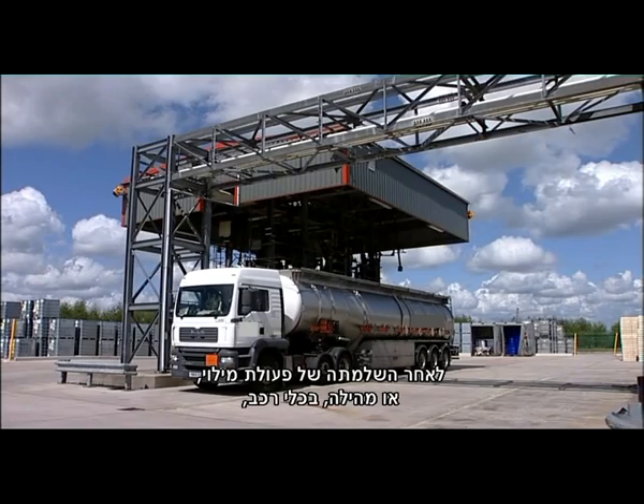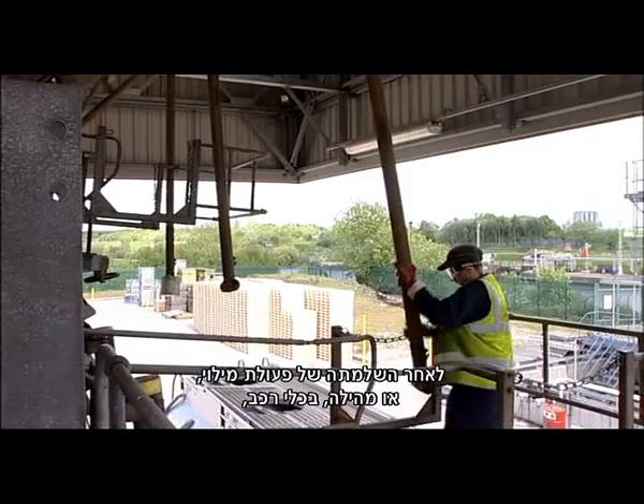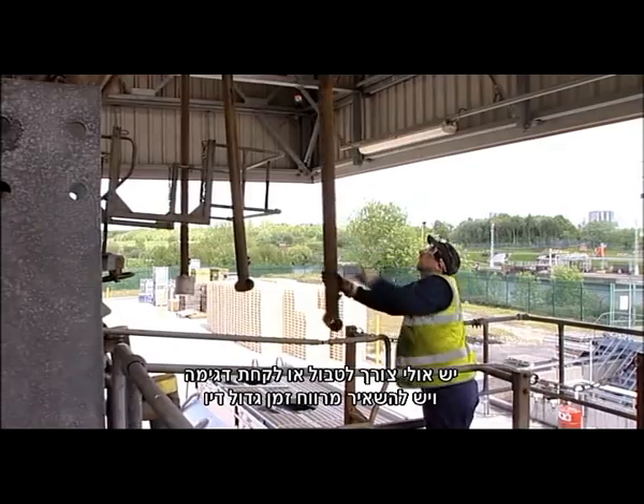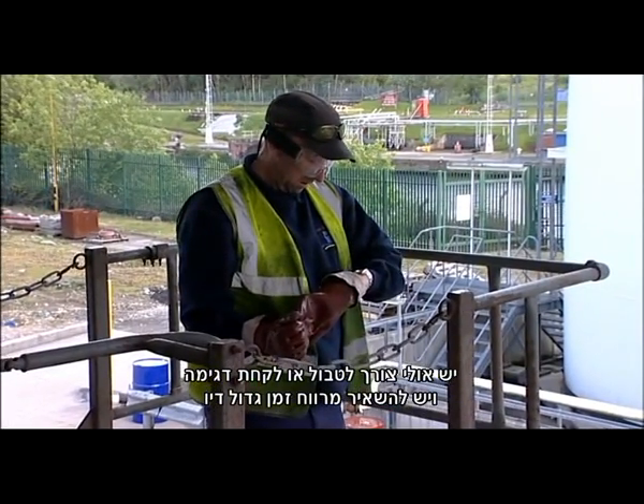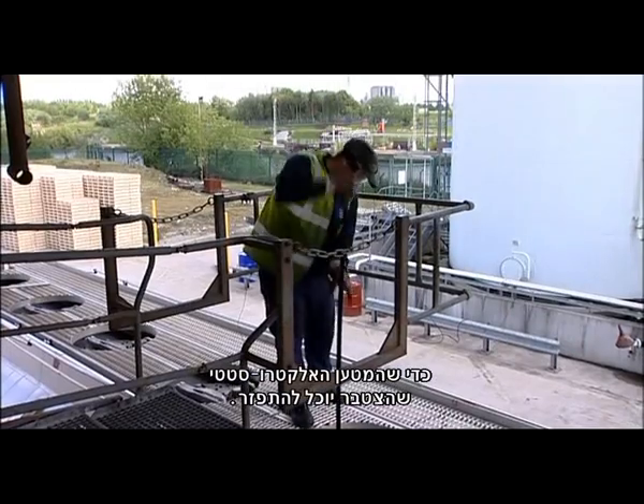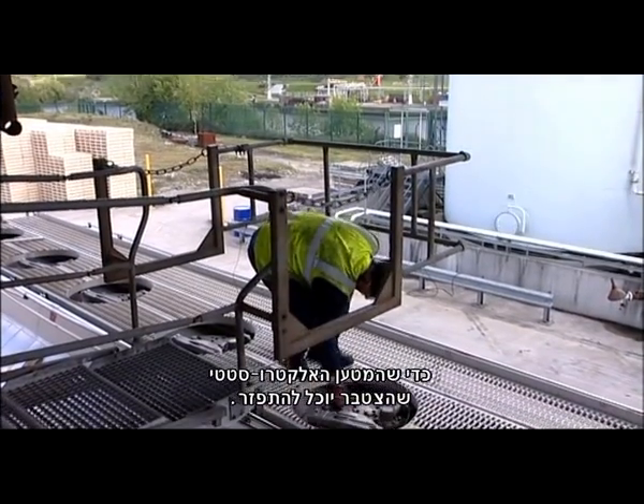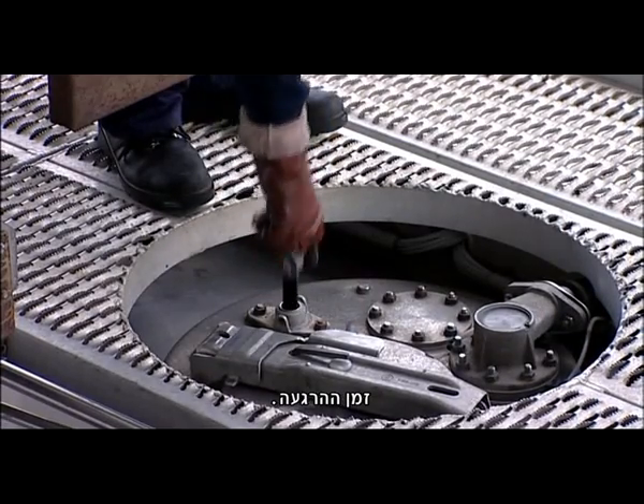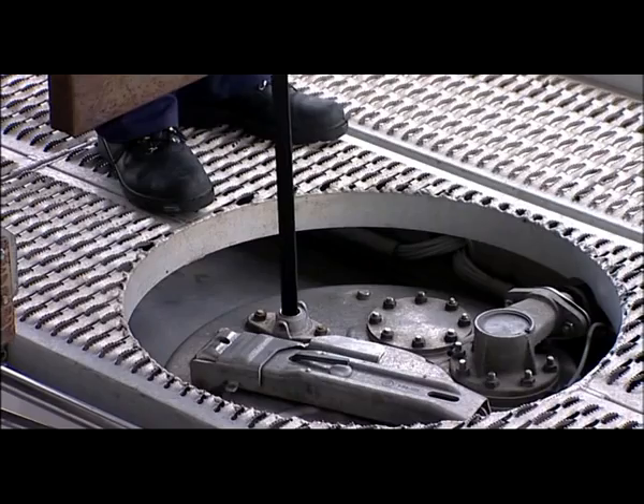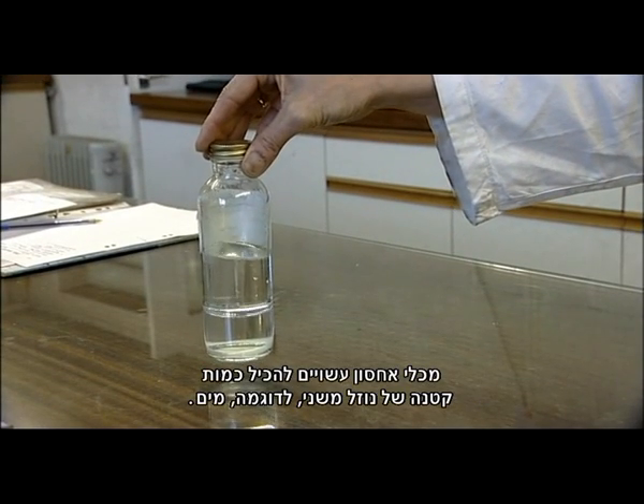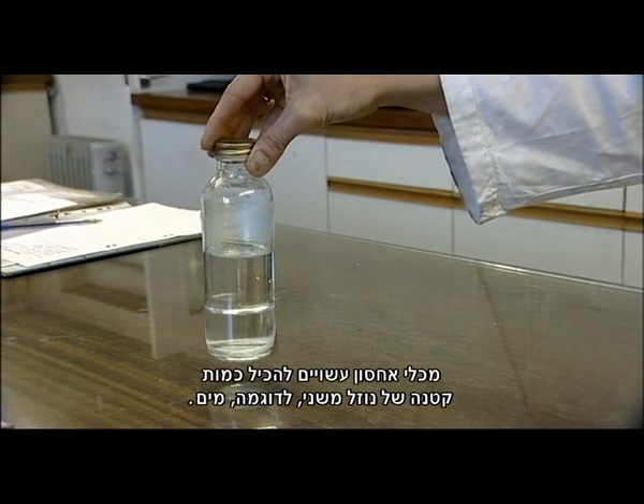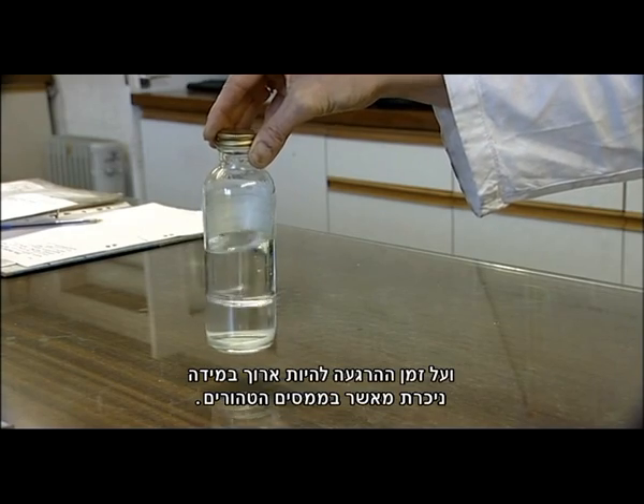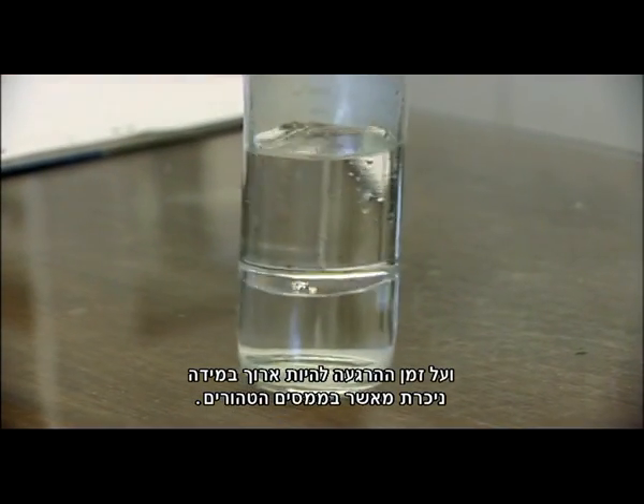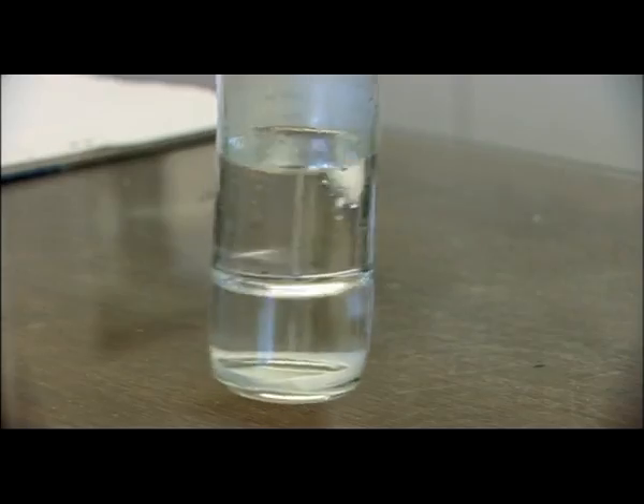Once a filling operation has been completed or a vessel has been mixed, it may be necessary to dip or sample, and a sufficient time should be allowed for the accumulated electrostatic charge to dissipate. The charge relaxation time. Storage tanks can contain a small amount of second phase, for example water, and the relaxation time should be considerably longer than for the pure solvent.